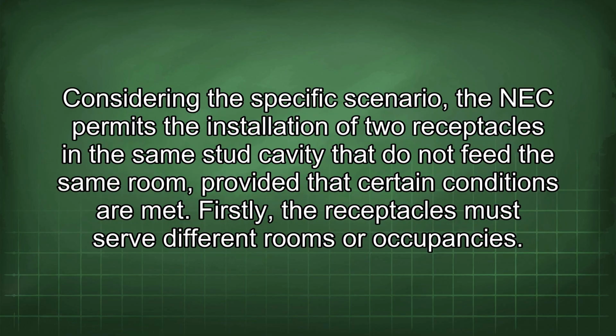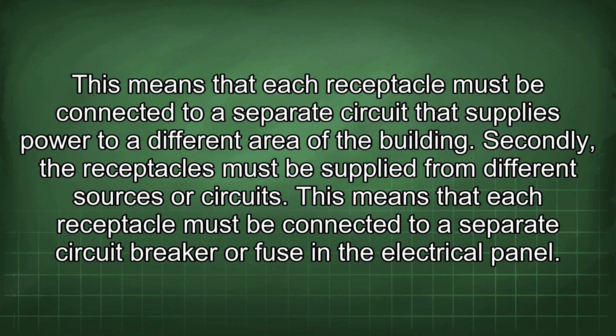Considering this specific scenario, the NEC permits the installation of two receptacles in the same stud cavity that do not feed the same room, provided that certain conditions are met. Firstly, the receptacles must serve different rooms or occupancies. This means that each receptacle must be connected to a separate circuit that supplies power to a different area of the building.